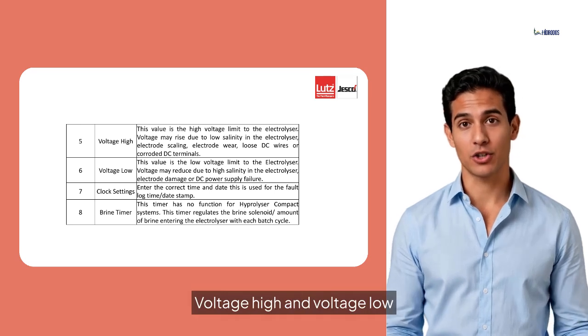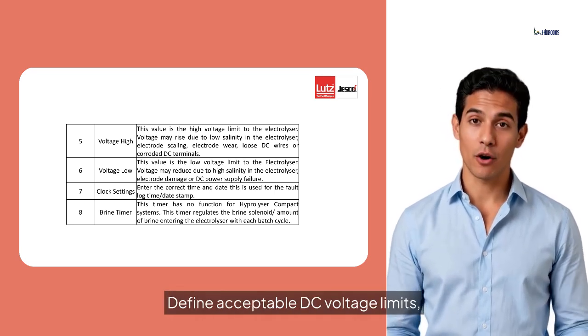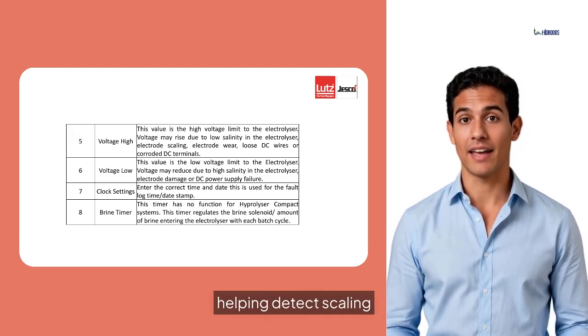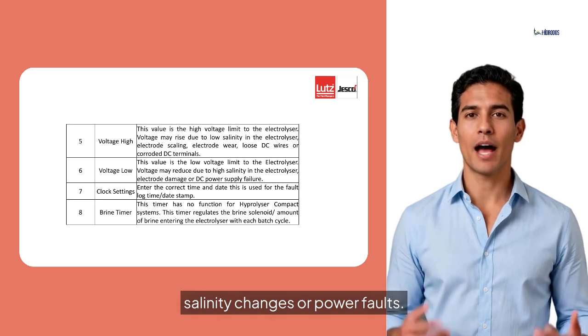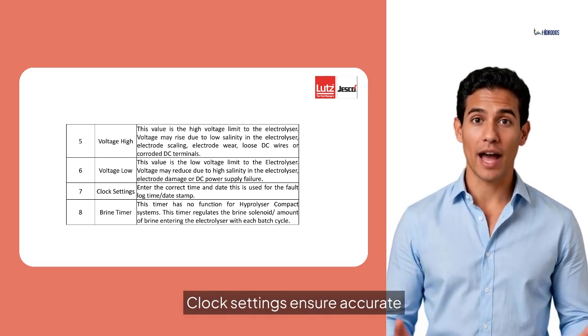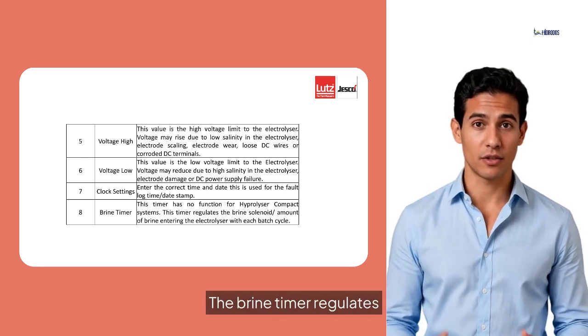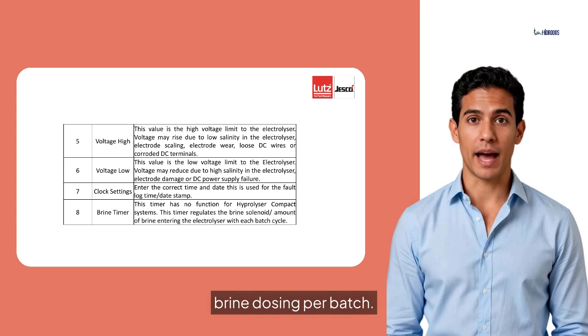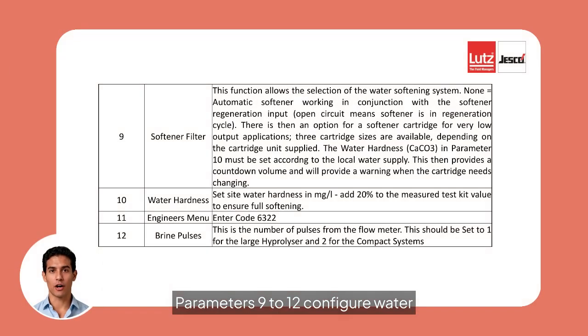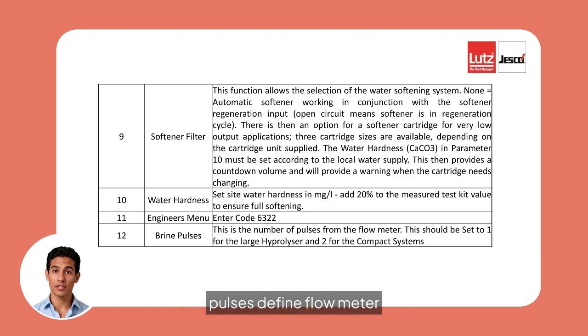Voltage high and voltage low define acceptable DC voltage limits, helping detect scaling, salinity changes, or power faults. Clock settings ensure accurate time-stamped fault logs. The brine timer regulates brine dosing per batch. Parameters 9 to 12 configure water softening and brine metering. The softener filter setting selects the softening method. Water hardness is entered in mg per liter to size regeneration. The engineer's menu is password protected, and brine pulses define flow meter pulses per volume of brine.